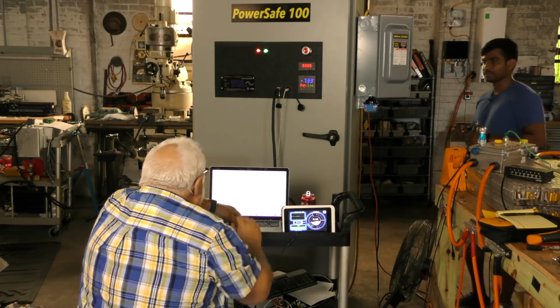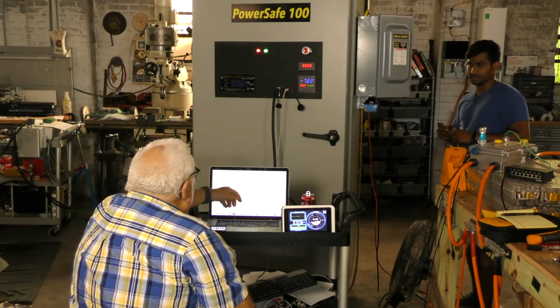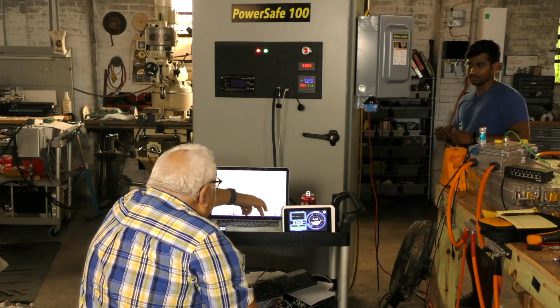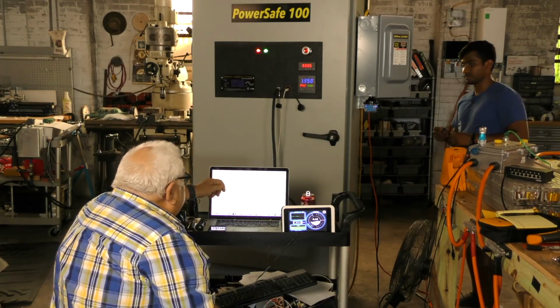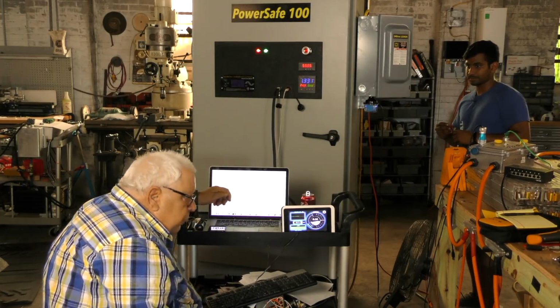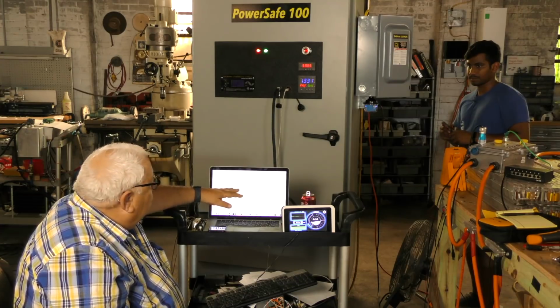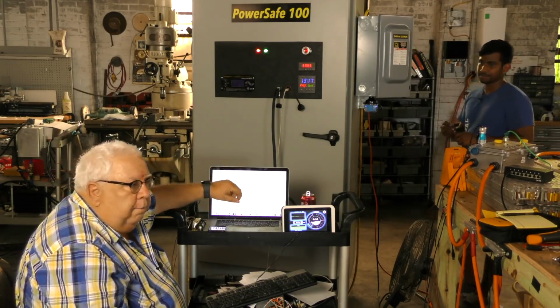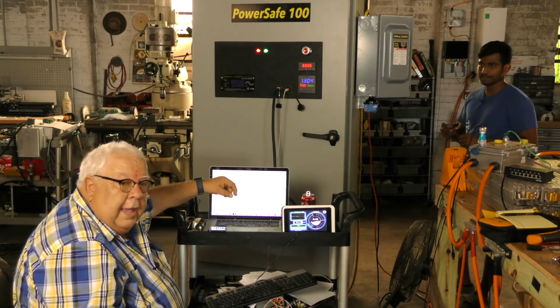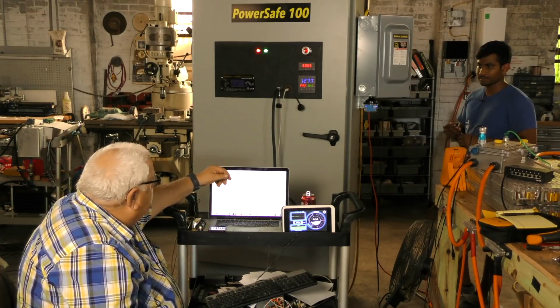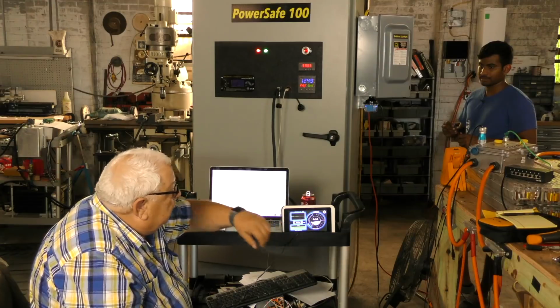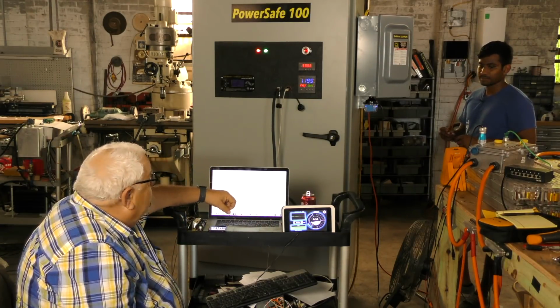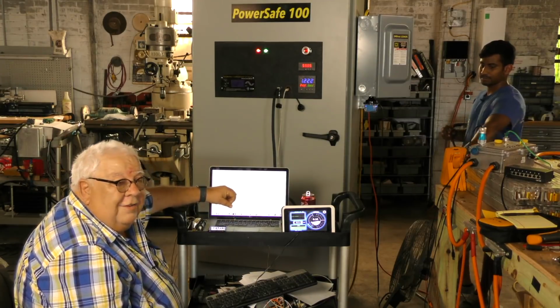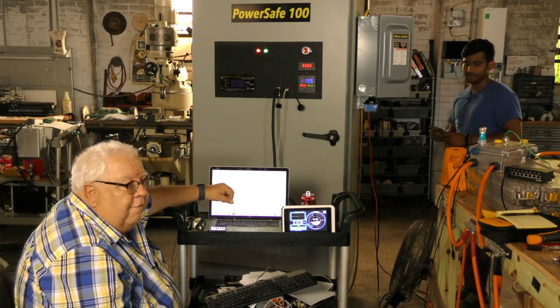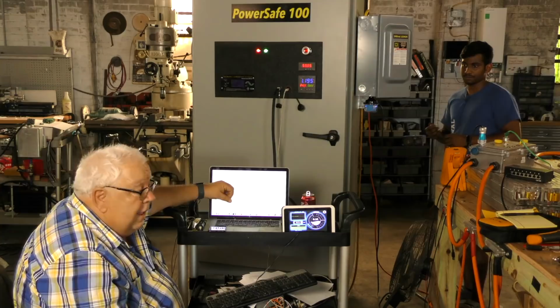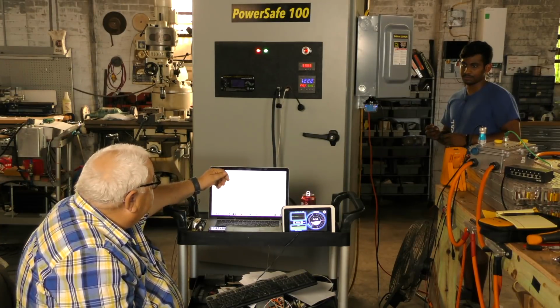Now let's go back over here, we're all up at 3.3 and so forth. I can set my charge enable to off, and what that does is cut off my connection. With charge enable off, we're not connected to the Enphase IQ7 - actually just one leg is opened up, and we're sitting here discharging at 3.54 amps, which reads as 4 amps on the display, at 145 watts discharge, just to have the inverter lit and be running our BMS. So we're using some power there.